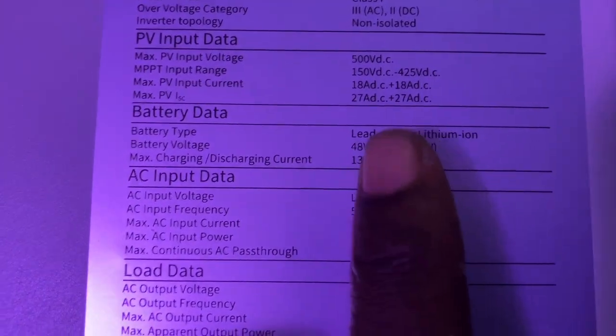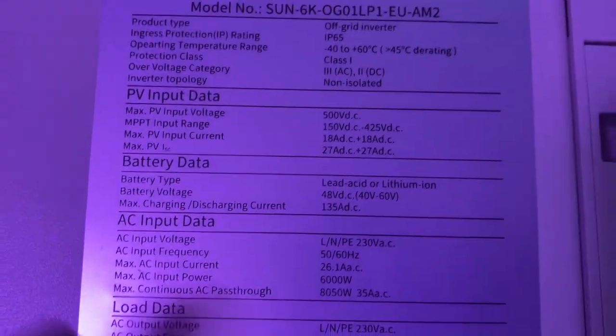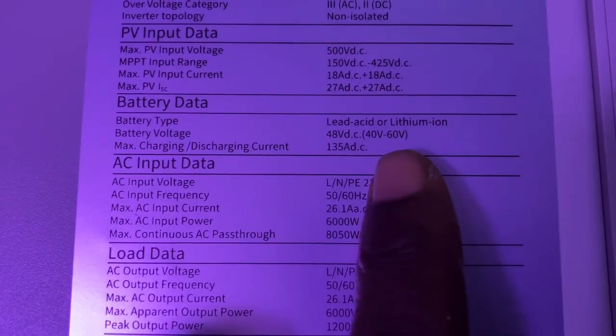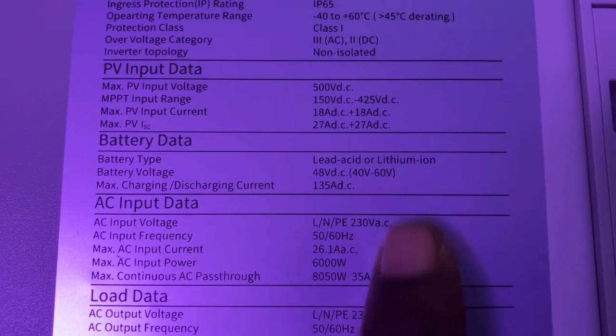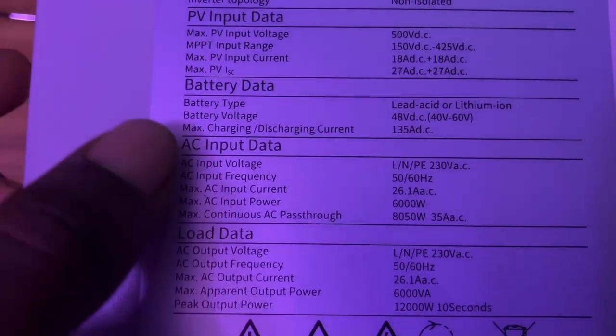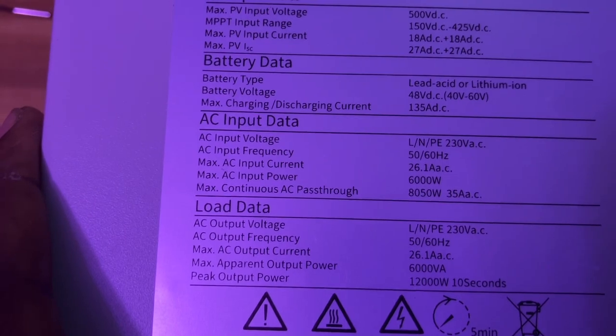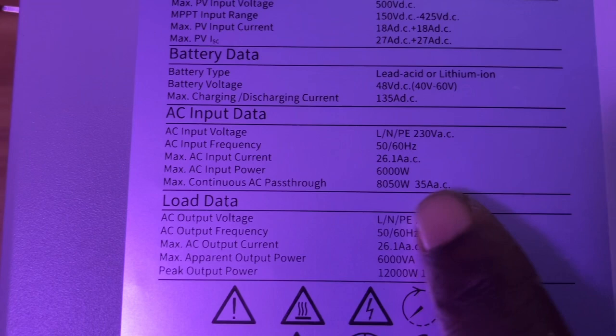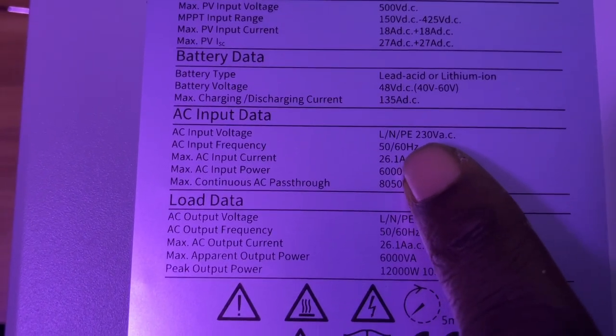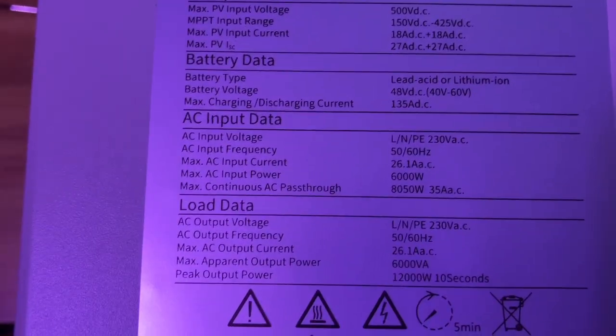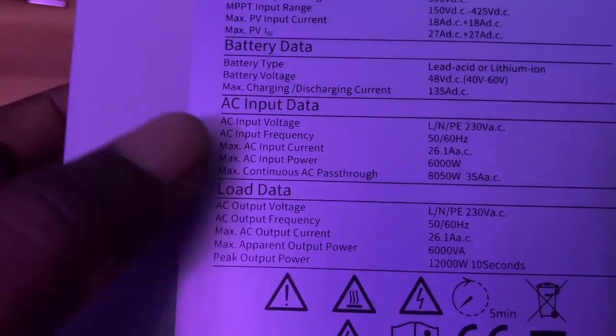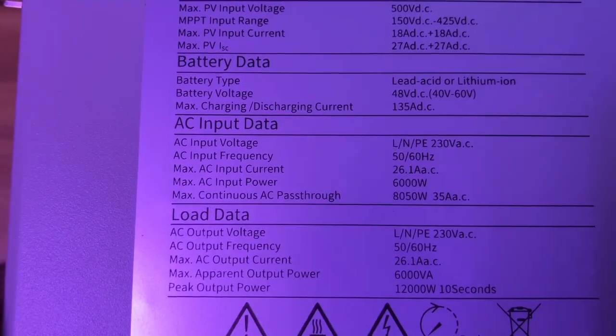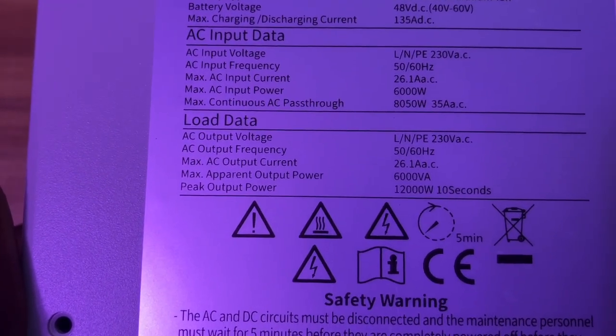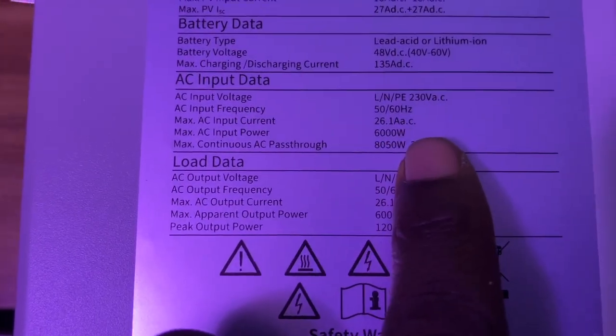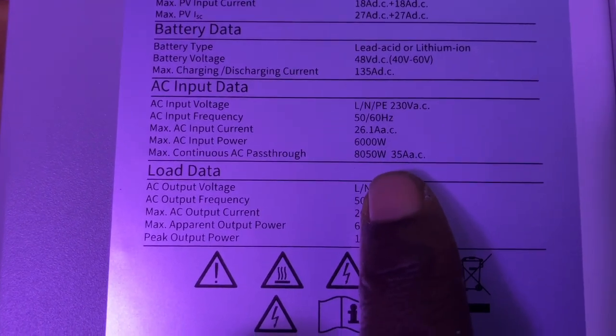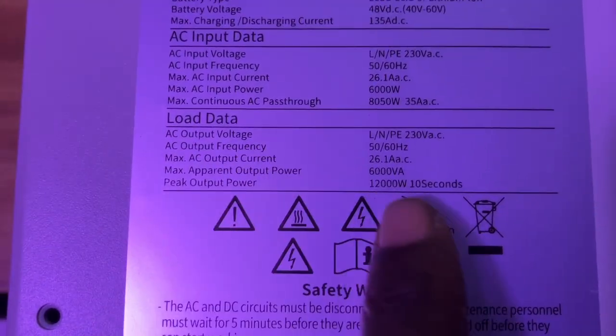Battery type, you can see here, you can either use it with lead acid or lithium. The battery voltage is also 48 volts, and you can do from 40 volts to 60 volts. That's the operating range. And we have the maximum charging and discharge current of 135. So the input voltage here is 230, and the frequency is either you selecting 50 or 60 hertz, and you have this input current of 26 amps, and the maximum input power is 6,000 watts, and it can pass through 8,050 watts. So you can see on the load side as well.